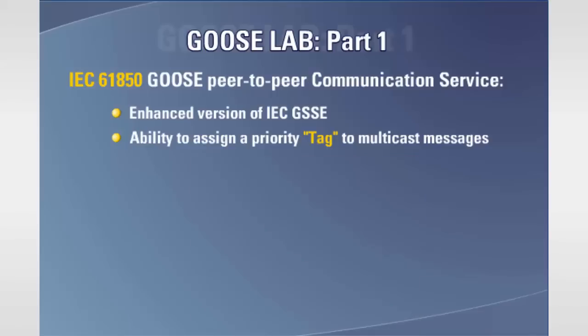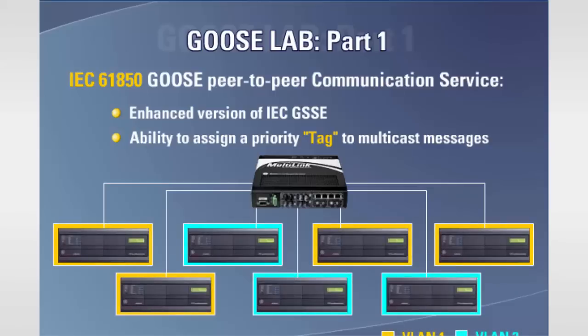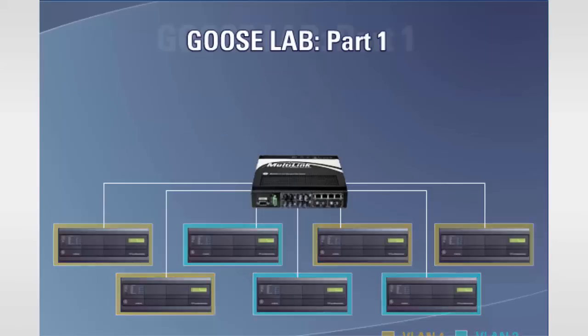The tag will allow the use of what are called tagged virtual LANs or VLANs. Virtual LAN technology allows us to separate the logical connectivity from the physical connectivity. The devices are still connected via physical cables, but the connectivity is now controlled through the VLAN configuration software of the devices. The VLAN can be port-based, meaning the VLAN is determined by the physical switch port the device is connected to. The VLAN can also be tag-based, meaning a tag is sent as part of the message with the tag determining which VLAN the message will be sent to by the switch. We'll start by configuring the switch's IP address, tagged VLANs, and priority.